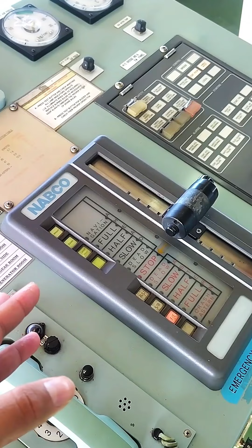One more engine limitation, guys, is that your engine RPM should be brought up and down gradually. Okay, because a large difference of temperature between the inner and outer wall of the piston and liner results in high thermal stress that may lead to premature failure of your cylinder liner and piston, guys. That's why RPM changes must be gradual, but if some situation demands, you must make it quickly to avoid immediate danger. So this is also a limitation.